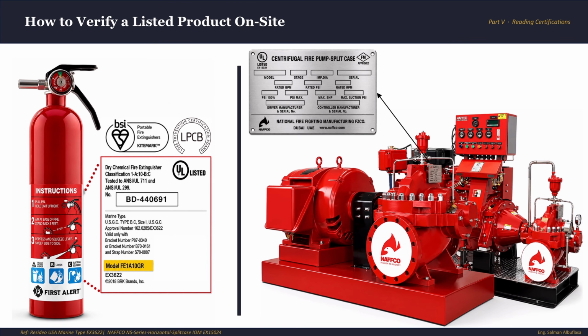Now, let's look at the fire extinguisher on the left to see what I mean. You can see they are listed, model number and file number. And you can also find different markings on the extinguisher, for example, an LPCB or BSI Kitemark. And different products carry their marks in a very different way. On extinguishers, they're going to be printed directly on the label, easy to see. A fire pump is going to have a metal nameplate bolted to the unit. Model, serial number, rating, and certification mark all in one place along with the manufacturer identification.